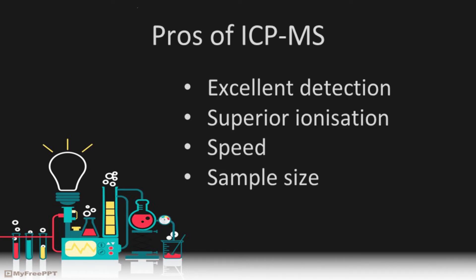Advantages of ICP-MS include excellent detection rates — it can detect concentrations as low as one part in 10 to the 15, or parts per quadrillion, for certain isotopes. Superior ionization: the extremely high energy plasma source provides very thorough ionization, meaning samples are fully decomposed into their constituent elements and converted into ions. Speed: ICP-MS instruments are much faster than other analytical techniques; for example, some instruments can measure around 80 elements in only 3 minutes.